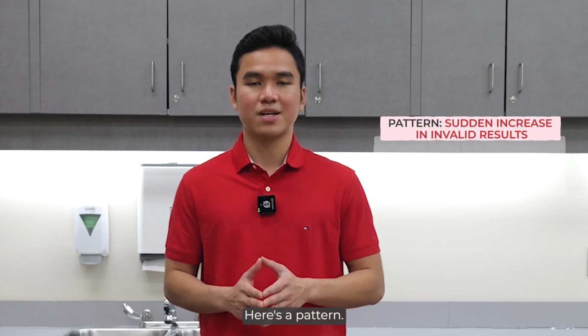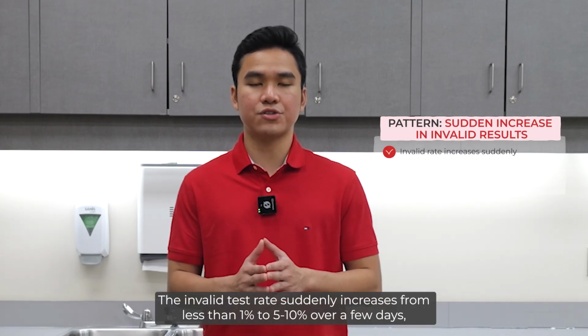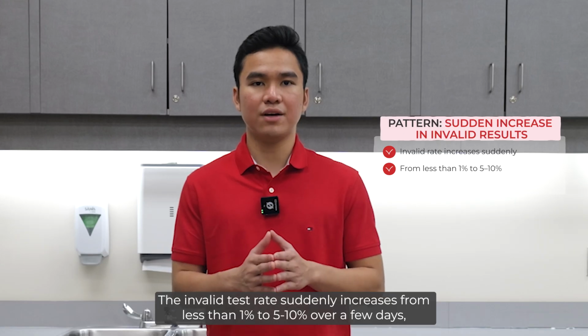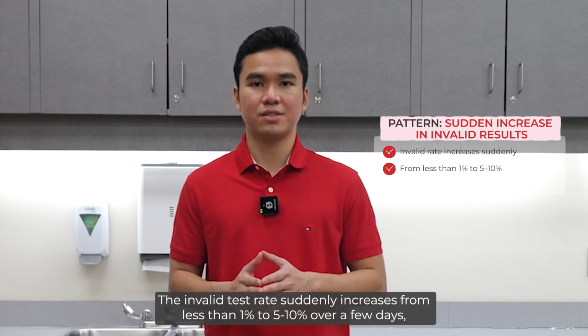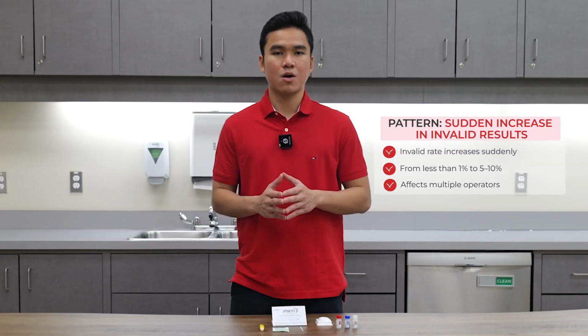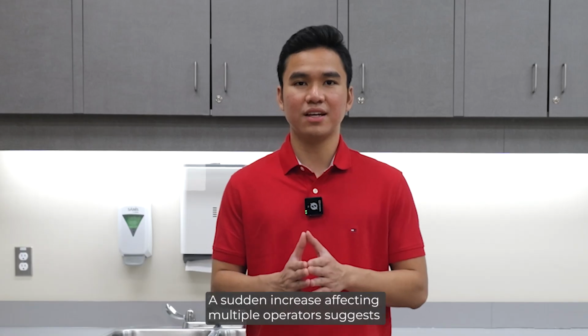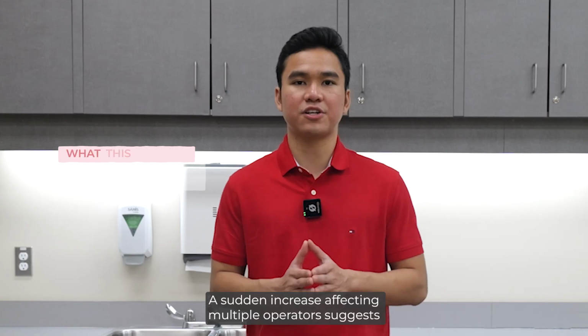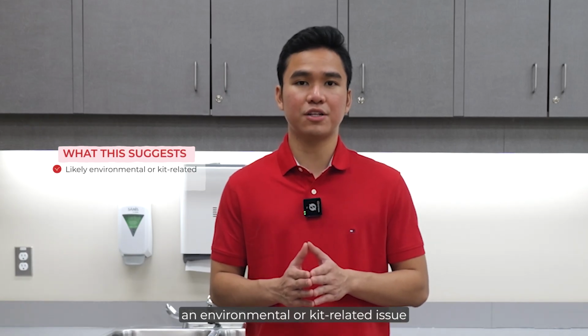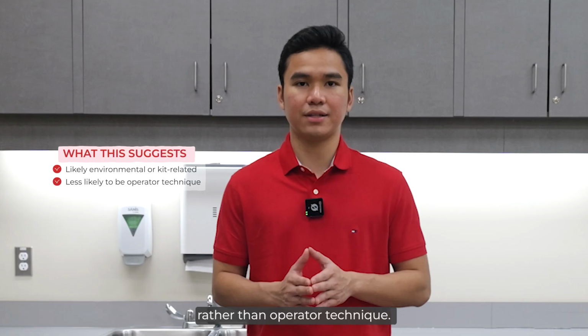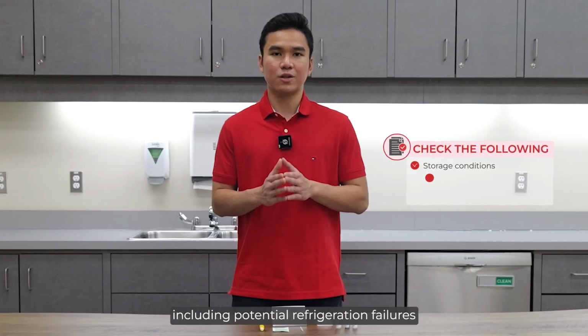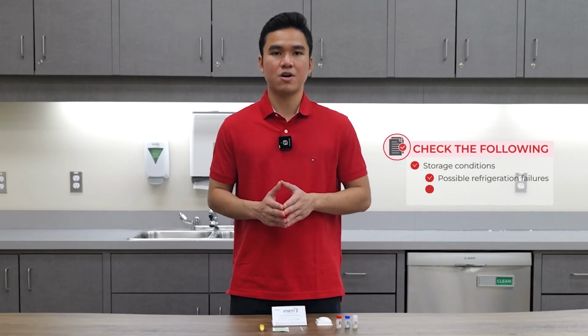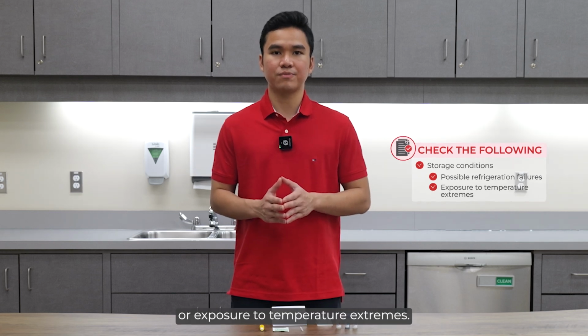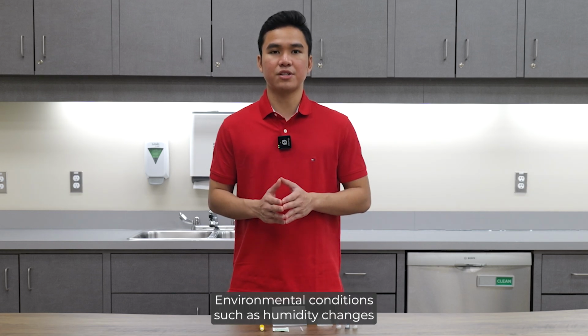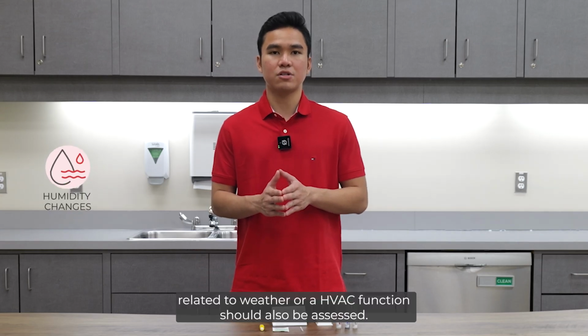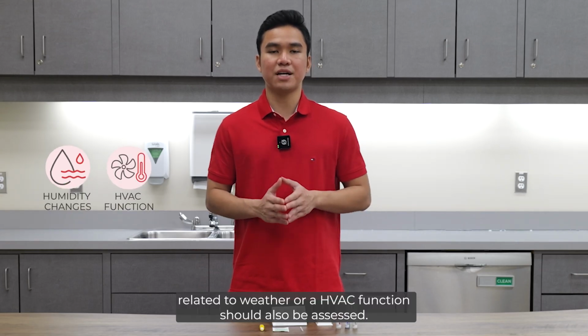Here's a pattern. The invalid test rate suddenly increases from less than 1% to 5 to 10% over a few days, affecting multiple operators. What does this pattern suggest? A sudden increase affecting multiple operators suggests an environmental or kit-related issue rather than operator technique. Check storage conditions, including potential refrigeration failures or exposure to temperature extremes. Environmental conditions such as humidity changes related to weather or HVAC function should also be assessed.